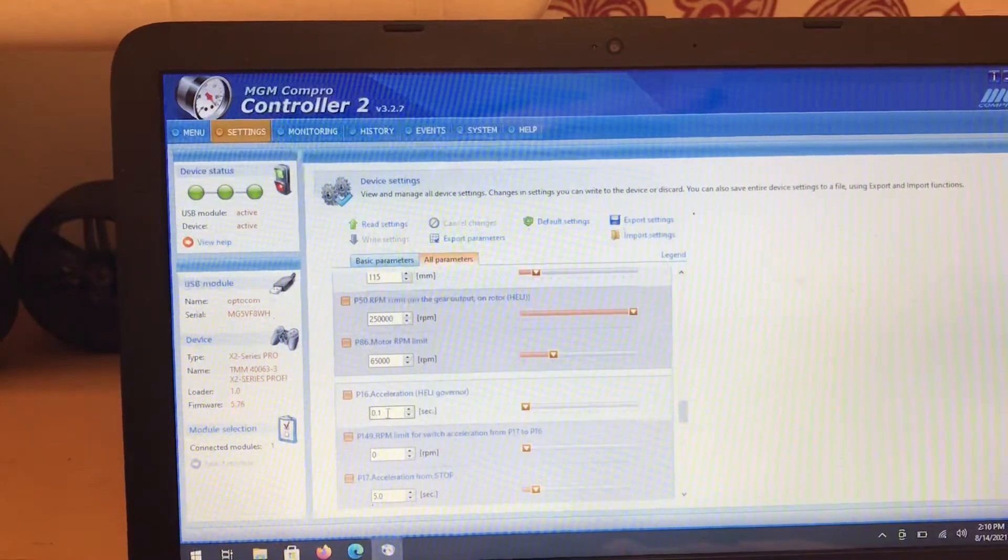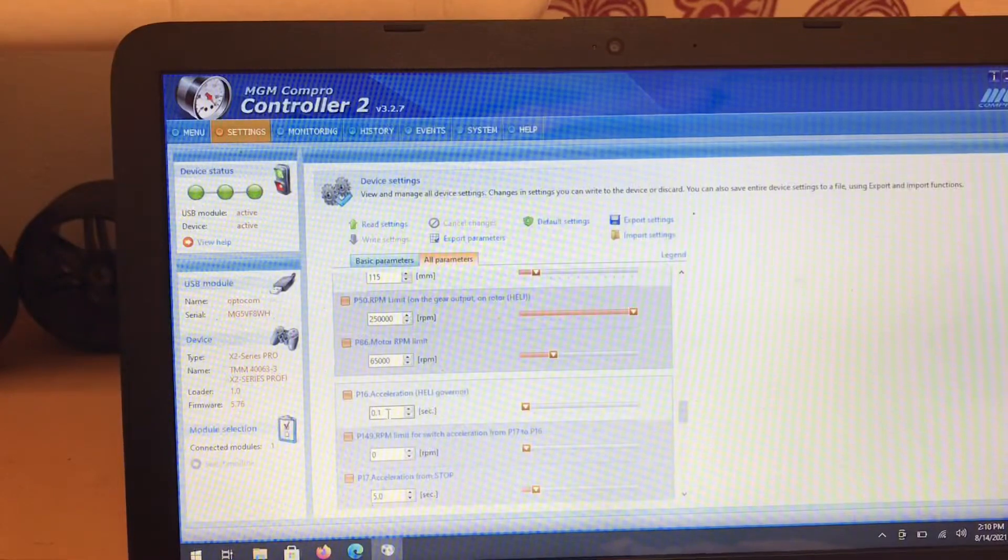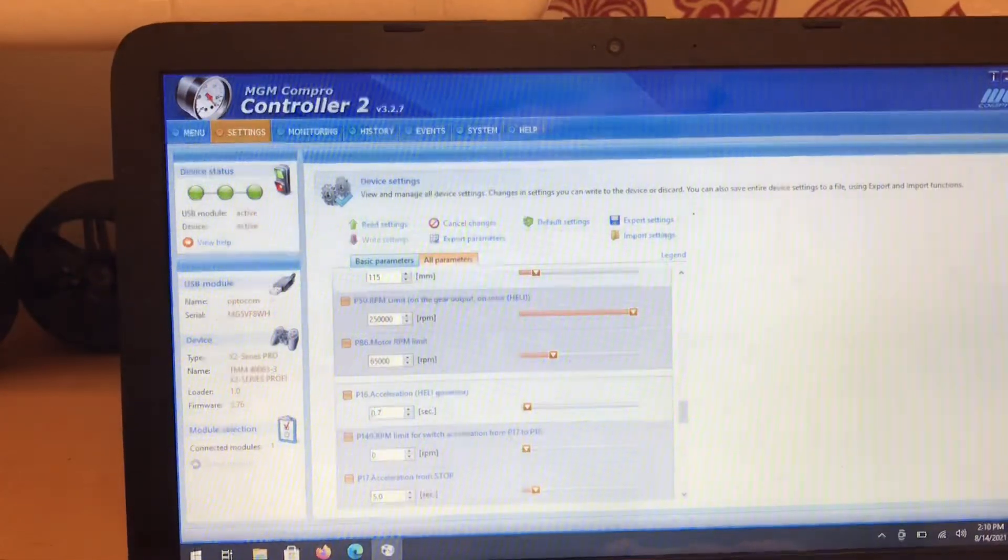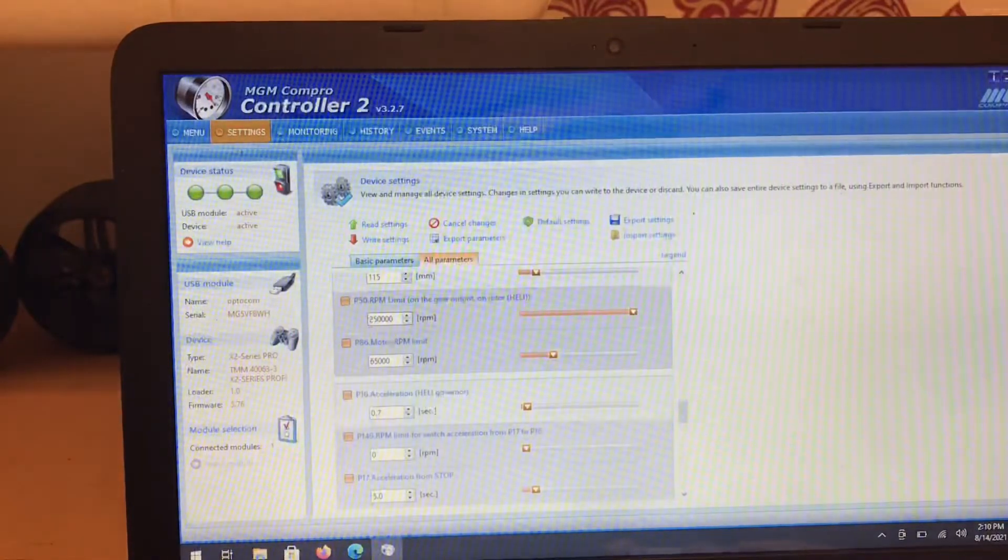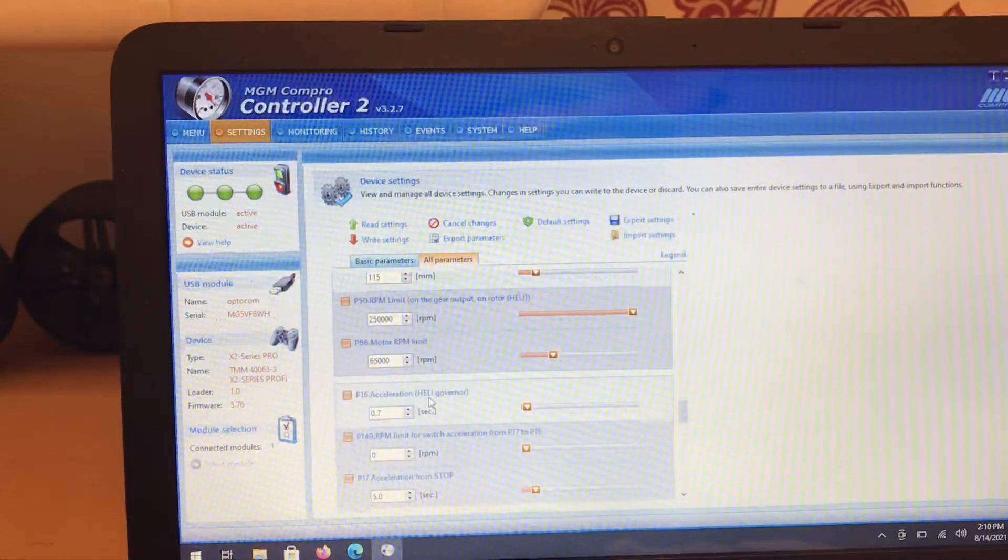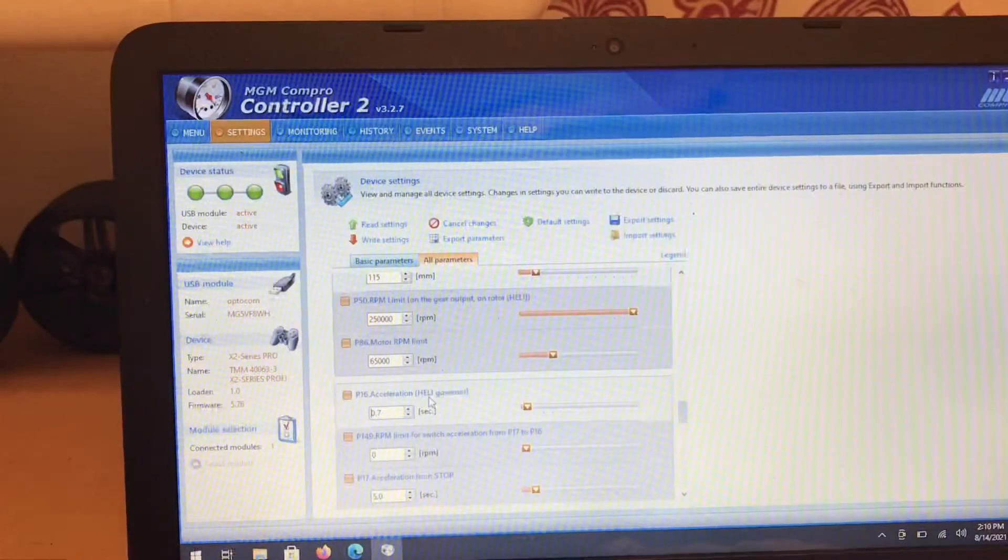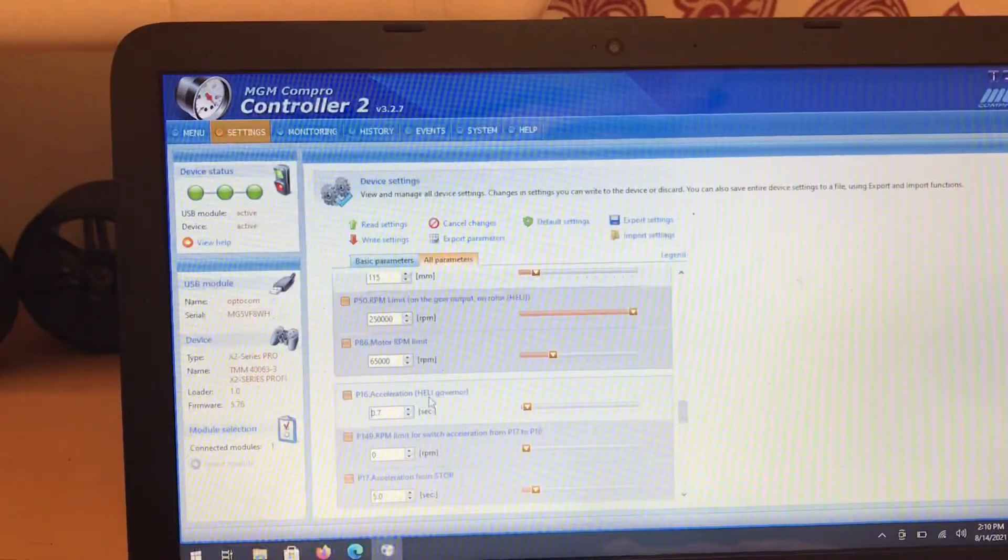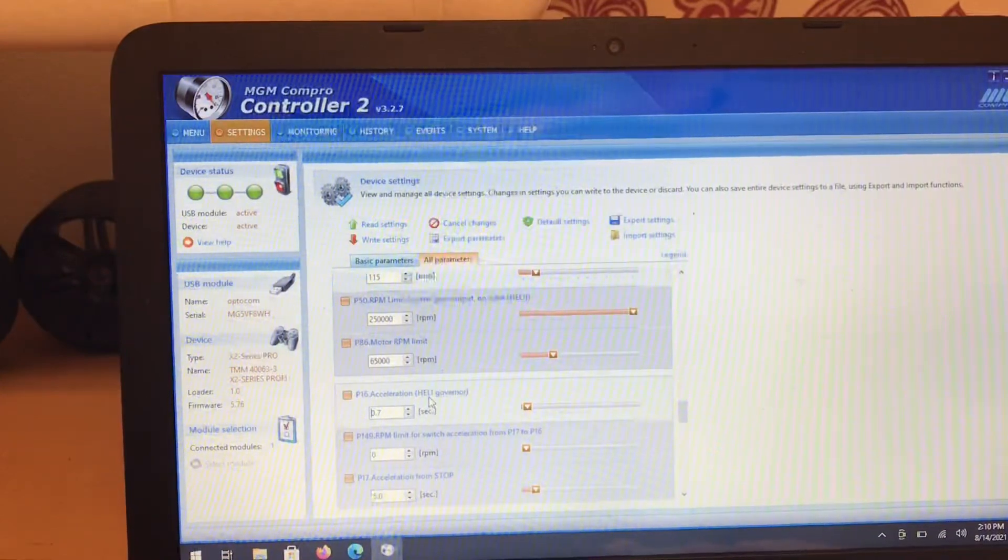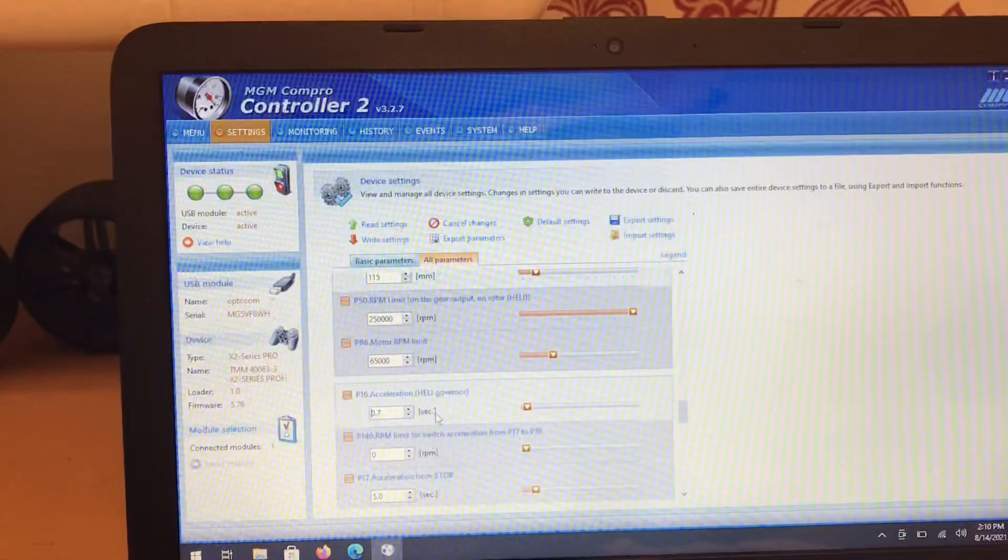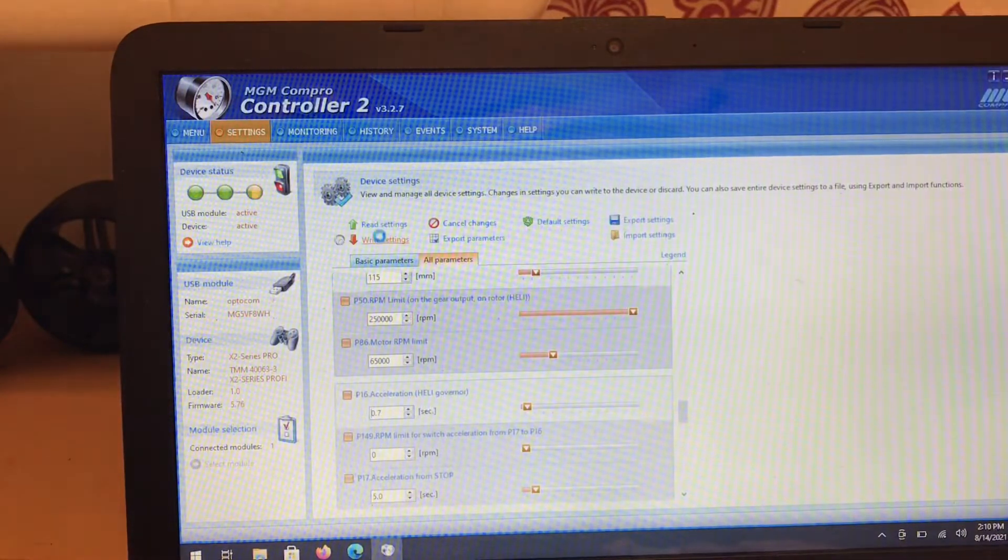So this is something you have to play with. On mine, I've already played with it, so I've realized that 0.7 of a second to full power is what keeps me out of cutting off due to high amperage. But this is here on the bench. Once I start driving it on the street, things change. I might have to up that just to keep it from shutting down like that. So we're going to write these settings.